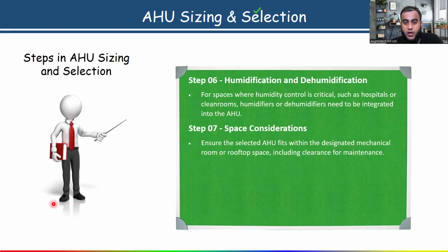When you are placing the AHU, you have to remember how much space you have to maintain between the room and the AHU. Is my screen visible clearly? Tell me, please. So ensure the selected AHU fits within the designated mechanical room, or if you're placing it on a rooftop, that you have that much space, including clearance for maintenance. So now the question is, how much clearance do we have to maintain? That also is given.